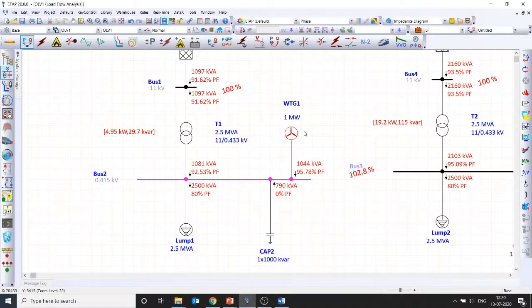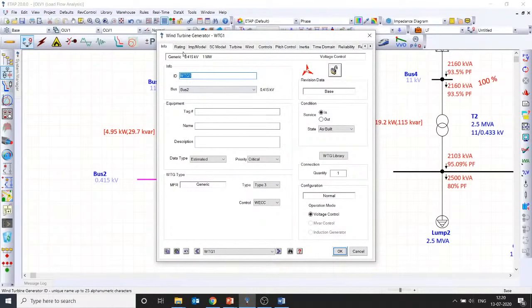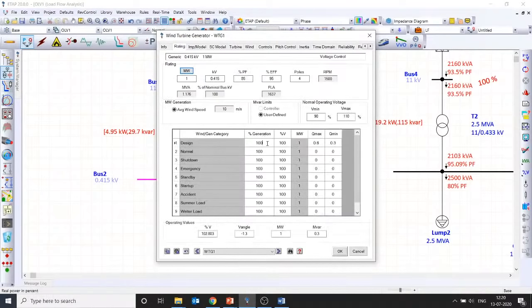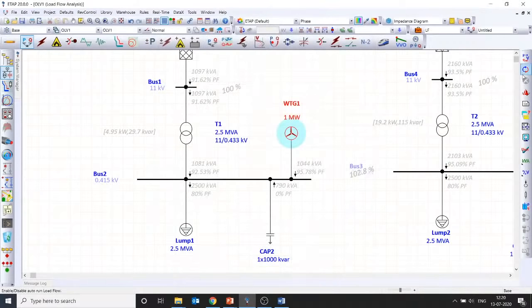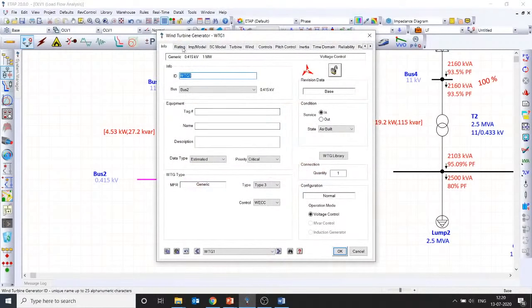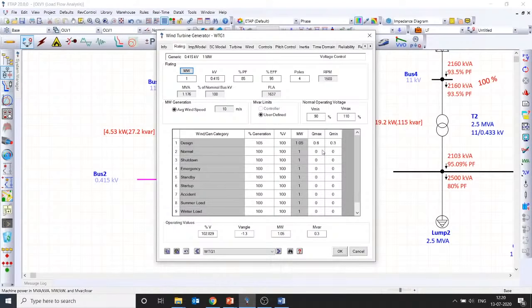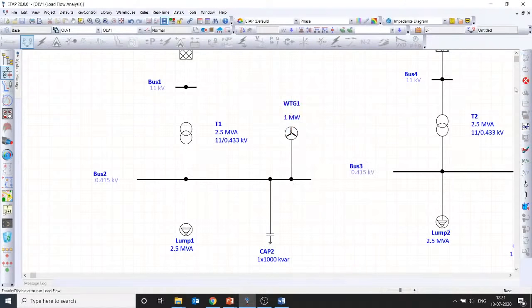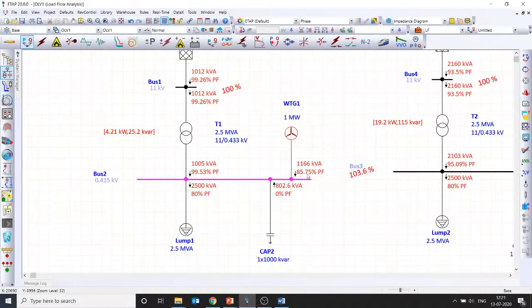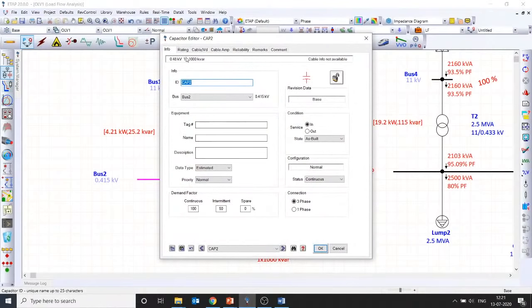That's because the generators are able to generate much more reactive power. And even this 1000 kVAr is not really needed if you carefully align the generator terminal voltage. So let me set the wind turbine generator terminal voltage to, for example, 105 so that it generates the maximum reactive power capability a doubly fed induction generator can generate. That's because of the reactive power max which I have given, it couldn't go beyond it. Sorry, it is the voltage I should have changed. Now you can see the wind turbine generator generates better reactive power and you are able to maintain unity power factor. So if a 0.9 power factor alone is sufficient, you can further reduce your capacitor bank rating.